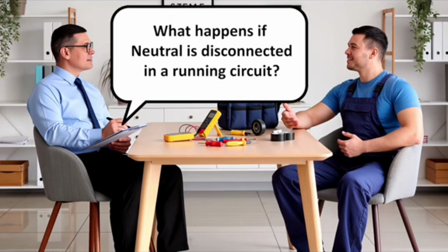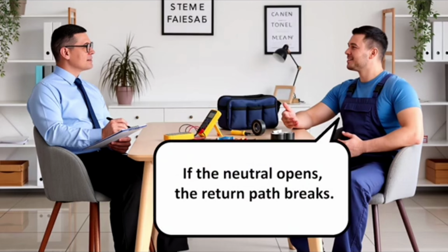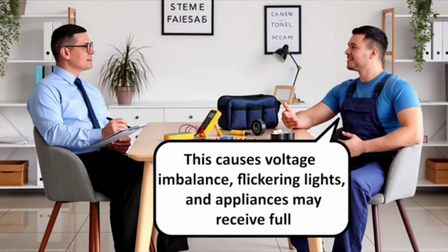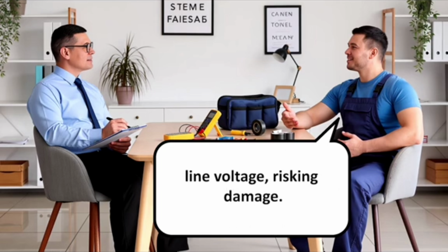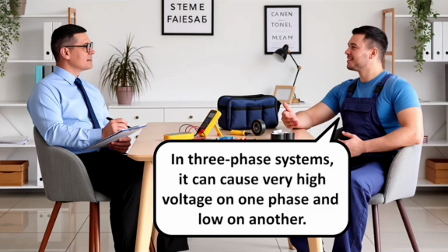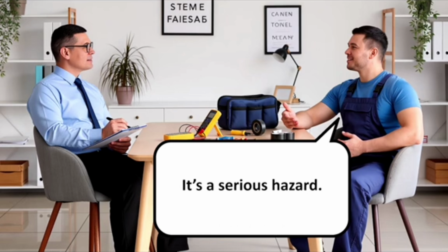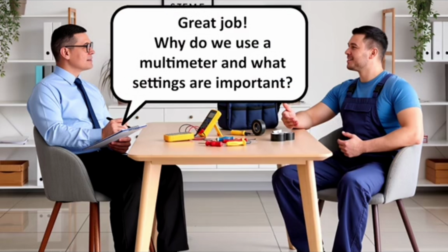What happens if neutral is disconnected in a running circuit? If the neutral opens, the return path breaks. This causes voltage imbalance, flickering lights, and appliances may receive full line voltage, risking damage. In three-phase systems, it can cause very high voltage on one phase and low on another. It's a serious hazard. Great job.